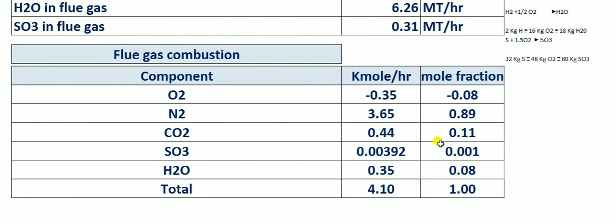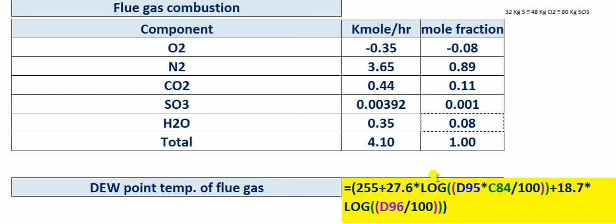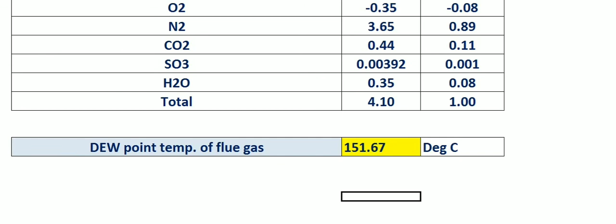Only this SO3 and H2O, and then total pressure, because the partial pressure of SO3 and the partial pressure of water, if you multiply by the total pressure, we'll get this dew point. That's it. Use this same formula, don't vary it. Just enter the SO3 mole fraction, no need to put 100. The H2O mole fraction also, no need to put 100. If you use percentage, you want to put 100 into total pressure, that is the flue gas pressure just before the stack entry. So 151.67 is the flue gas dew point. We want to maintain above this temperature to avoid condensation and to avoid cold end corrosion.